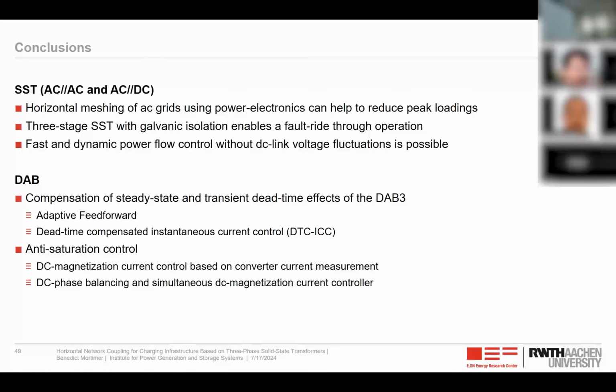And yeah, we also saw that a fast and dynamic power flow control without the DC link voltage fluctuation is possible. And with this control, I think we can in the future also go to setups where we have reduced DC link capacitors. Because the control can be so fast, we can reduce maybe 60 or 70% of the DC link capacitance that we had in our prototype.